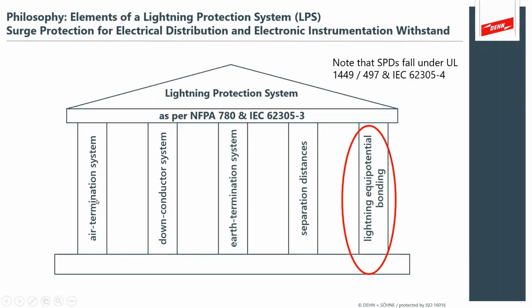And allow me, the air termination system. Ben Franklin introduced this in 1753 and immediately put it out in the public domain in the Farmer's Almanac, and described how to do an air termination, a down conductor, and an earth termination rod, like an earthing rod, and described them as suitable to serve as the external lightning protection of the day. It saves countless lives from fire. And what wasn't as abundant, and certainly not understood at the time, was that you need to make sure to separate your lightning from your other electrical devices. Now, in 1753, there weren't many. Now there's lots. And so these two that people pay the least attention to are actually incredibly important for us in our modern world.